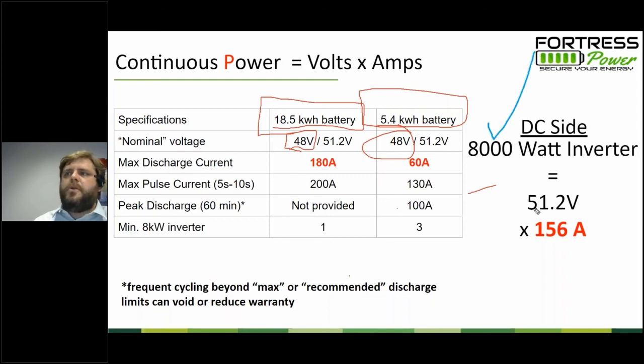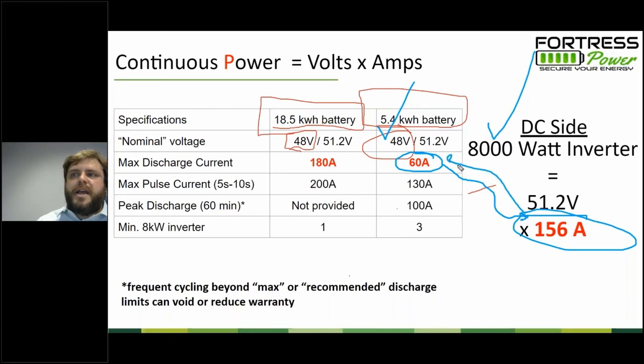And so a very common sizing error that we see, especially for first time installs, is you'll just say, okay, I have a 48 volt battery inverter and I have a 48 volt battery, and so they're compatible. And the shortcut that you shouldn't have taken was ignoring the continuous discharge current rating of the battery. So in this case, the inverter is capable of demanding a current that is 3 times greater than what the battery can actually supply. Now, in our case, we have a battery management system that'll disconnect the battery before any damage is done. But on a battery that didn't have that sort of battery management system, you could burn out the battery terminals, you could potentially damage the battery. More often, you'll heat up your battery cables and potentially start a fire by just matching 48 volts to 48 volts and not doing a more thorough design.